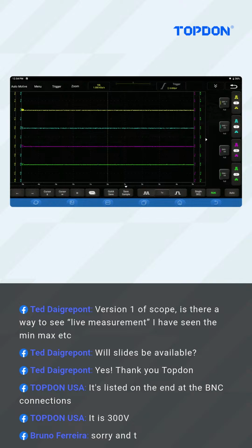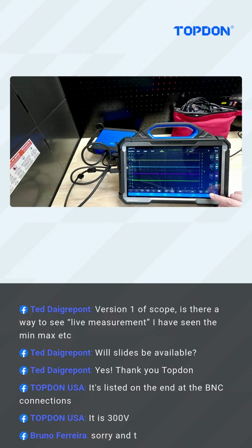The other thing that's really important to understand about the scope: you'll see on the very bottom right of the screen, and I'll switch back to the camera here so you can see where I'm pointing, on the very bottom right of the screen, you'll see a run button in green. It will change to stop if you freeze whatever you're looking at on the screen. Now, when you freeze it on the screen, you'll have a number of different things you can do. We can screenshot it, which of course is a super useful thing, right? Being able to save a screenshot right then and there allows us to catch a waveform right on the screen and email it out directly from the tool very quickly and easily. The other thing you can do is integrate those screenshots into a pre-scan, post-scan, or diagnostic scan.